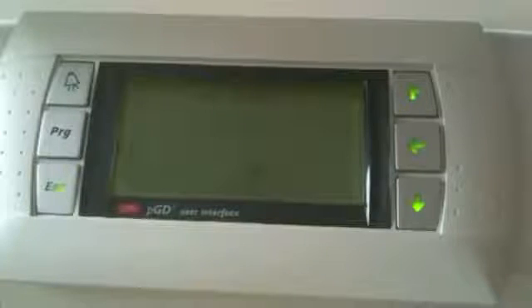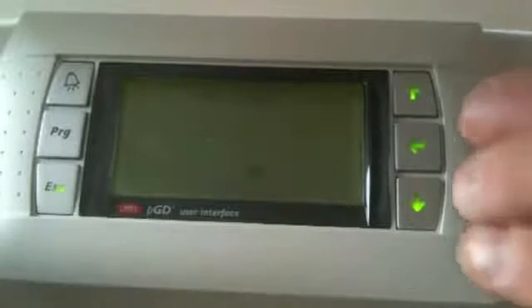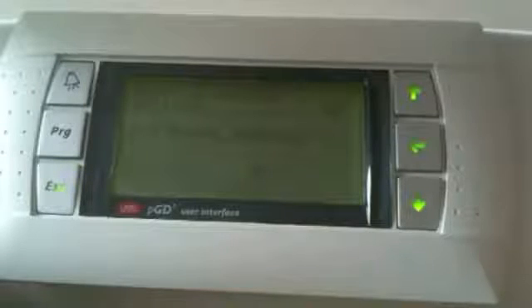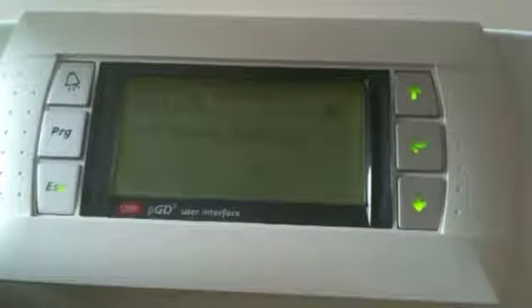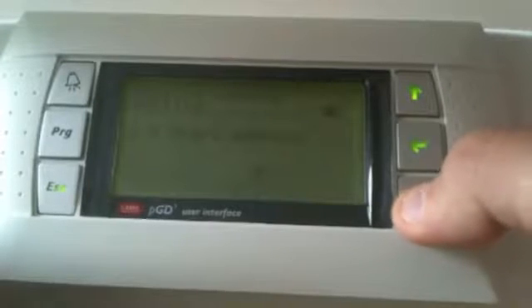The first thing I will do is temporarily set the address of the display to address 00. That is done by simply pressing the three buttons on the left-hand side together simultaneously until the following screen appears. You will see the cursor blinking on the top left-hand side. With the Enter button, my cursor moves to the next modifiable field, which I will bring back from 32 to 00.